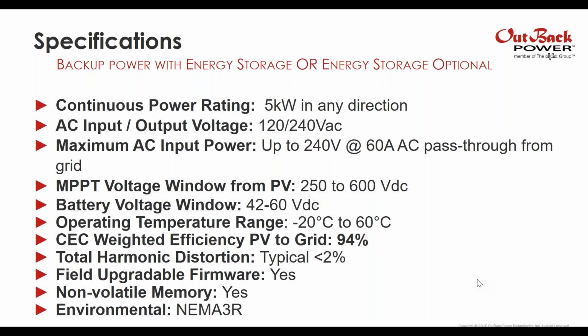With respect to specifications, SkyBox has a continuous power rating of 5 kW in any direction. It's 120/240. Maximum AC power input is up to 60 amps AC pass-through from the grid. So if you have a high surge load and you're grid connected, your excess surge capacity is met by the grid. SkyBox will support 5 kW for that load. MPPT voltage window, down as low as 250, up as high as 600. Battery voltage window is consistent with your traditional 48 volt batteries. So it's 42 volts, up as high as 60.